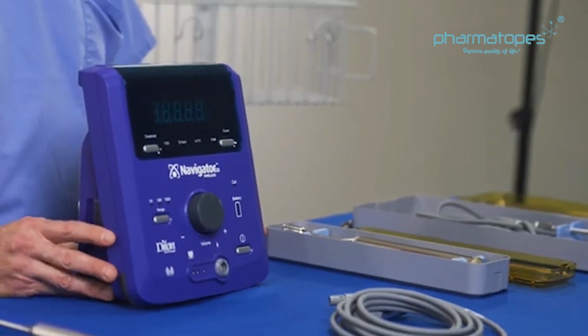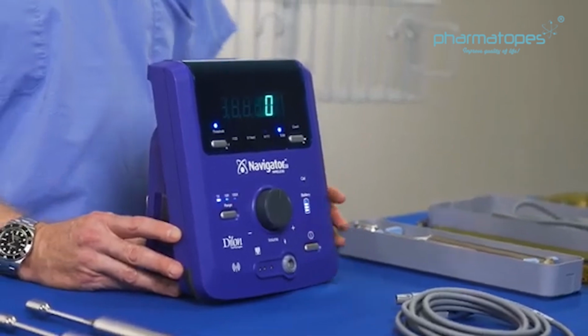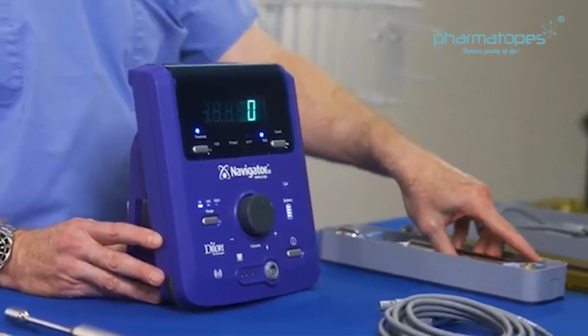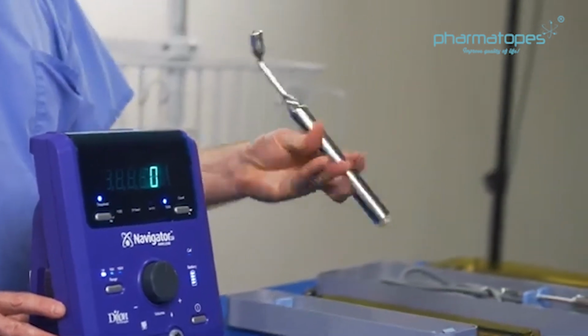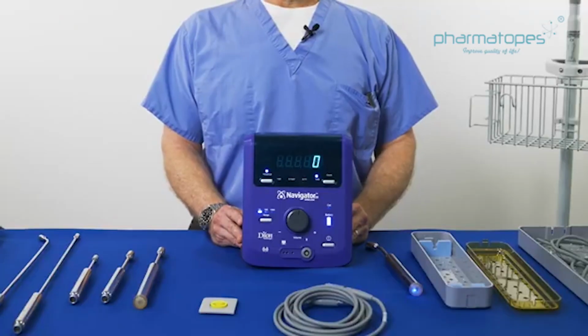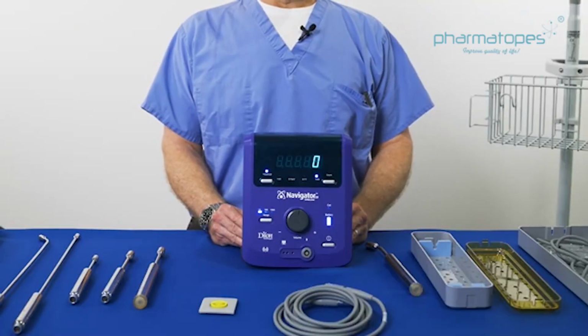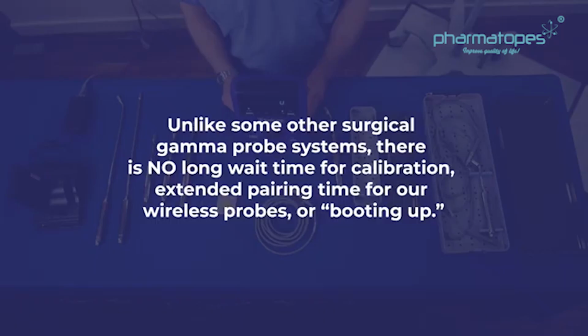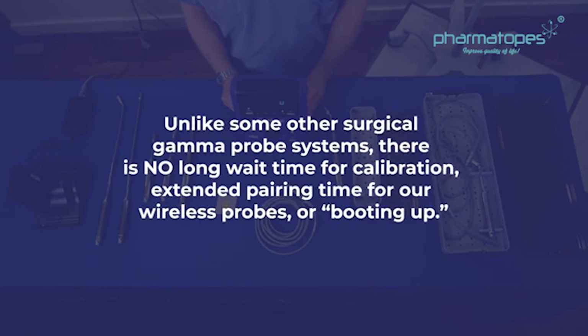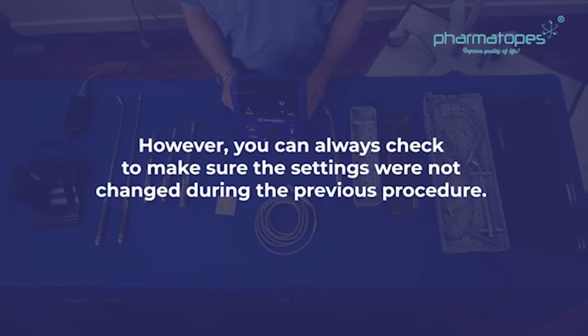First, turn on the control unit by pressing the on button. You remove the sterile probe in the sterile field, give it a light shake so that it links to the control unit. The settings on the control unit are preset, so you're ready to go instantly. Unlike some other surgical gamma probe systems, there is no long wait time for calibration, extended pairing time for our wireless probes, or booting up. However, you can always check to make sure the settings were not changed during the previous procedure. The scan knob is set to scan.